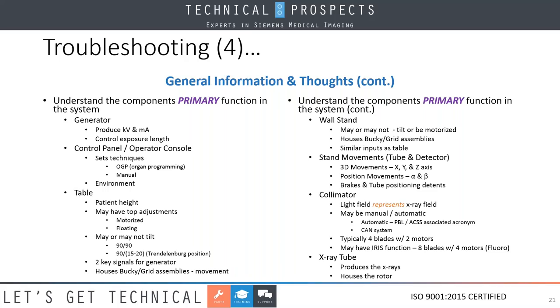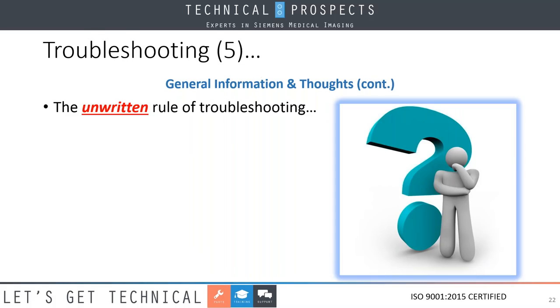Collimators typically have 4 blades and typically 2 motors, although there are exceptions to this. If you have an undertable tube for fluoro, it may have an iris function, in which case now you're going to have 8 blades and 4 motors to try to simulate a circle. It comes out more of an 8-sided stop sign. What does our X-ray tube do for us? It produces the X-rays and houses the rotor. Just that simple. So those are some primary functions.